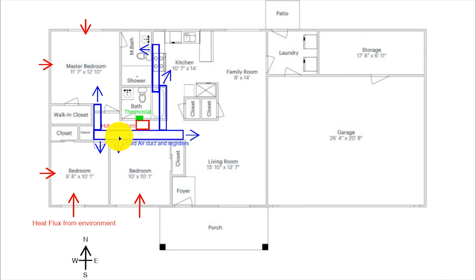The crack under the doors of the bedrooms is not big enough, and this causes the pressure in the bedrooms to be slightly higher than the rest of the house, and this directs a disproportionate amount of cold air from the AC to the main areas as opposed to going to the bedrooms.